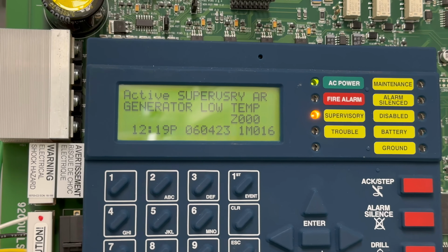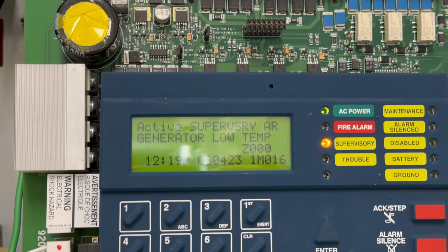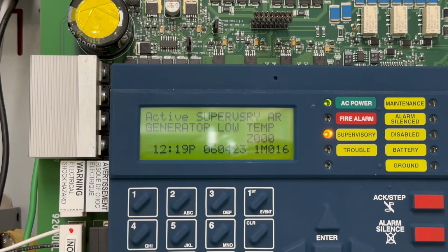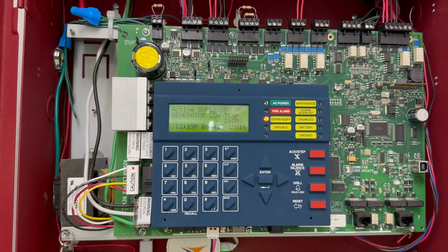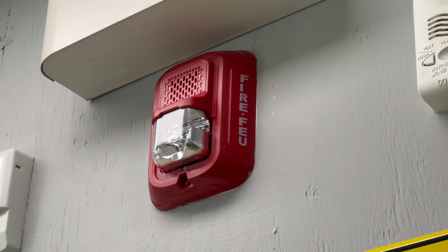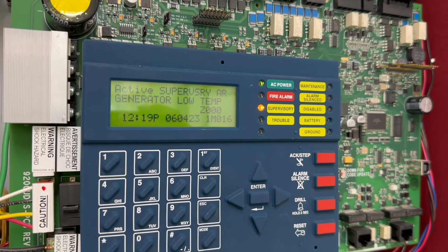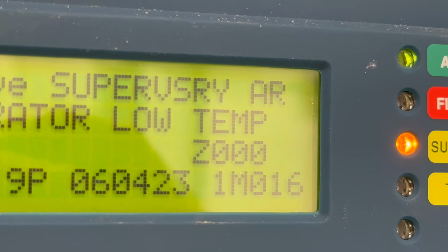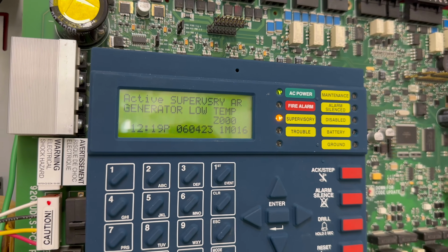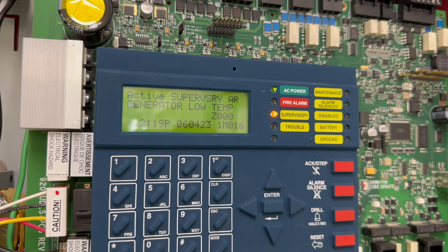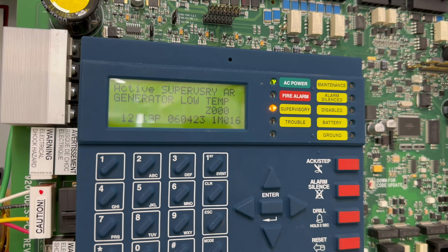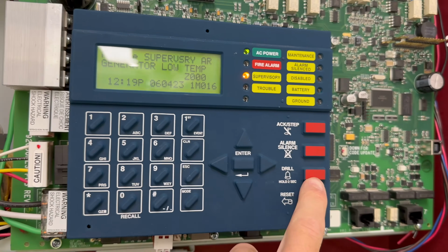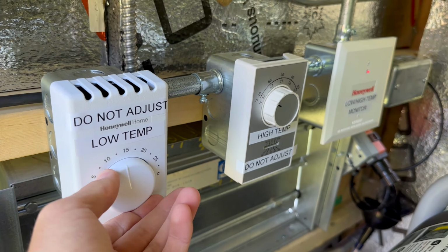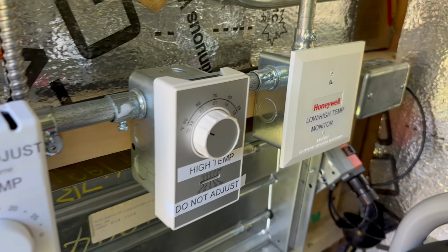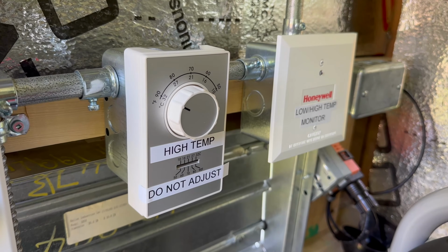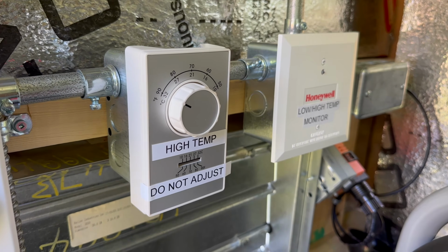Now, it doesn't come up as a fire alarm because there isn't a fire emergency. It is just coming up as a supervisory, which just beeps at the local panel and does not set off alarms on the rest of the system. The reason it says supervisory AR is that stands for auto reset, where it isn't a latching device. Once the trouble clears, it will go back to normal. You do not have to reset the system. The high temperature alarm will do the same thing and will come up as a high temperature alarm on the fire alarm panel.